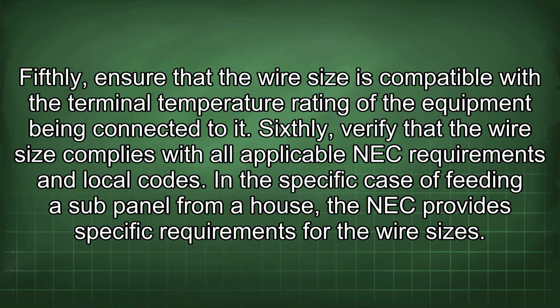Fifthly, ensure that the wire size is compatible with the terminal temperature rating of the equipment being connected to it. Sixthly, verify that the wire size complies with all applicable NEC requirements and local codes. In the specific case of feeding a sub-panel from a house, the NEC provides specific requirements for the wire sizes.